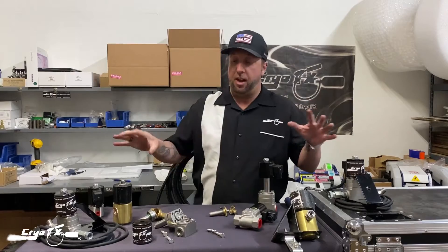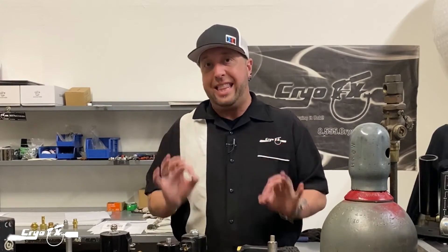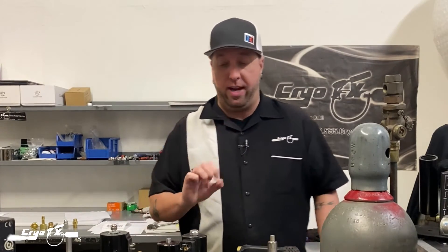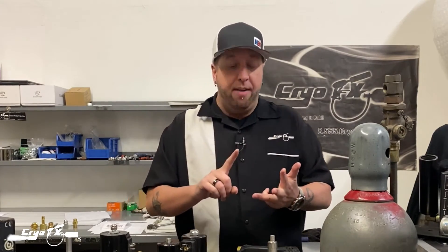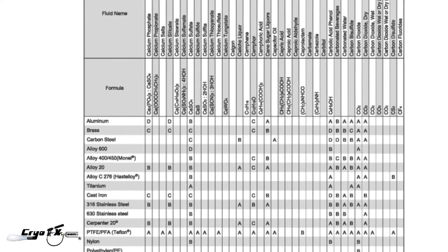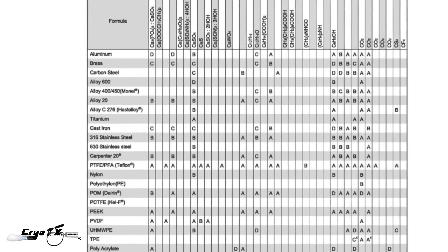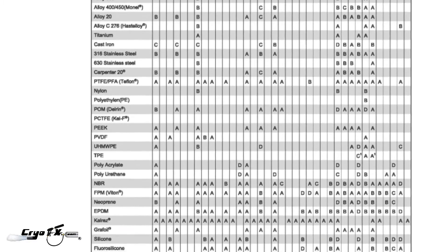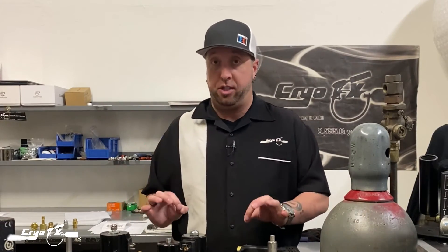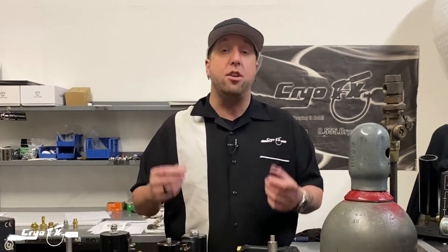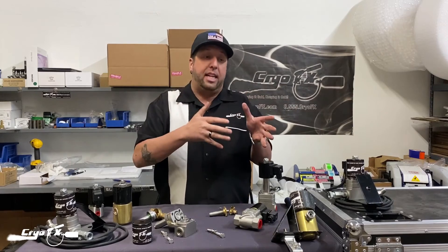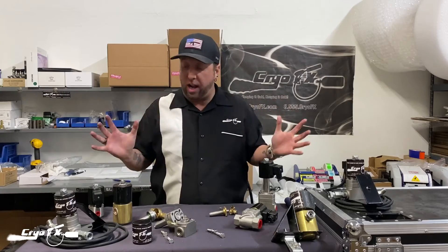When ordering valves, the most important things to consider are: seats and seals, valve type, working temperature, and the pressures the valve can hold. We'll put a reference guide in the description showing different seats and seals along with the temperatures and pressures they can handle. This is critical when dealing with cryogenic or liquid CO2 valves — super cold temperatures and different materials handle different temperatures differently. Your specific need will determine which valve is right for you.